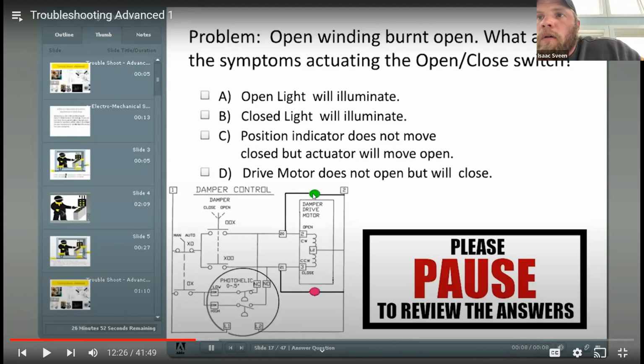Let's see, open winding burnt out, burnt open. I would say yes, since it's burnt open, right? This part's burnt open right here. Okay, so between T2 and L2 in that drive motor. So the light above it, the green light, would come on if you move your manual switch? Yep. Now, will your closed light, the red light, go on?